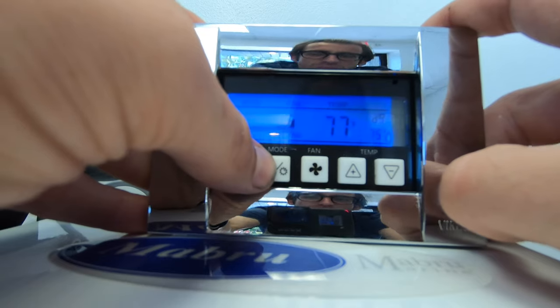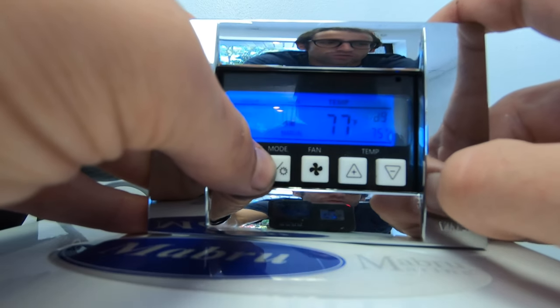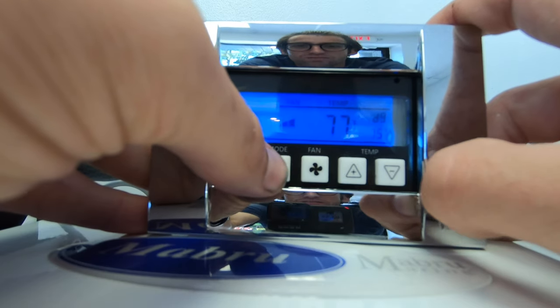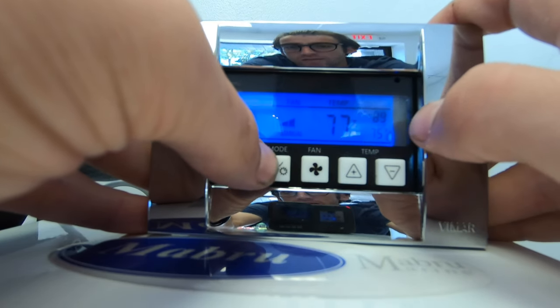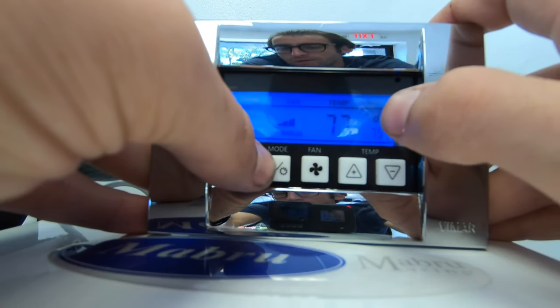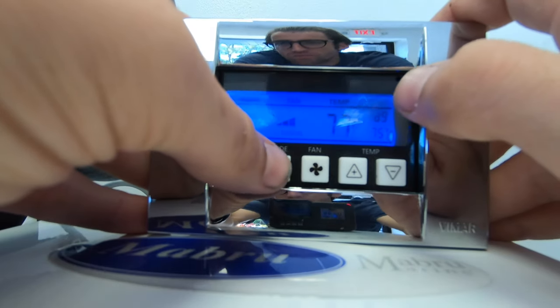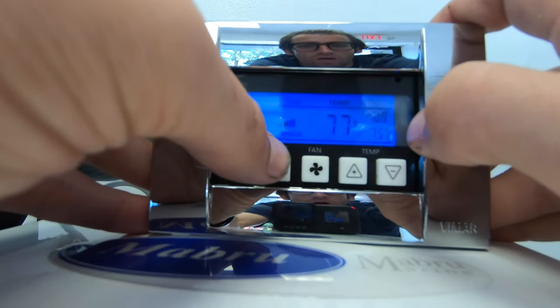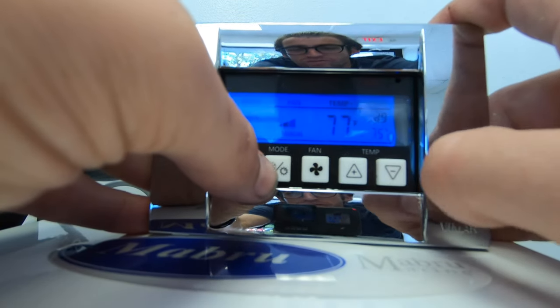Below, I would say my limit as far as low speed would be about 35, depending on duct complications. And the high, that's going to be based on customer preference as far as the velocity coming out of the blower. But we've gone as low on here as 55.